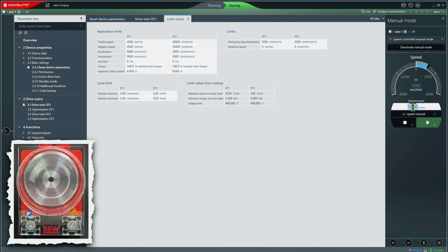I can also type in a speed directly, like 3,500 RPM. I can change direction just by putting a minus sign on that. And I can also use the keyboard to control manual mode. If I want to stop my drive, for example, I can hit F4 and it will bring it to a stop. Or of course I can click the stop button here. Manual mode is handy just for testing things out. Looks like our basic commissioning did succeed.